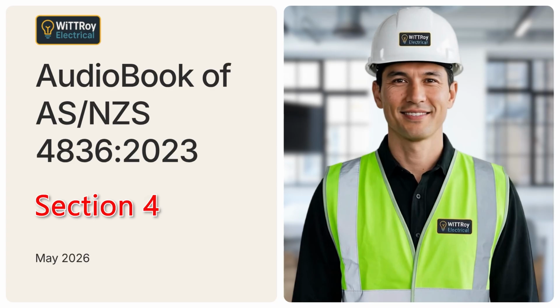Suitable PPE must be worn. The PPE must fit correctly and must be in good condition. All work on exposed energized conductors or live conductive parts must be done from a stable work position. If the energized electrical equipment has earthed metal, earthing continuity must be maintained. If earthing continuity cannot be maintained in the normal way, the work must follow an approved procedure. Temporary protective earthing conductors may be needed when an electrical component is separated from its normal earthed metalwork. Those temporary protective earthing conductors must be rated to withstand the prospective short-circuit current of the primary protection.